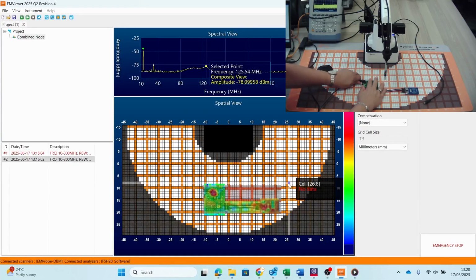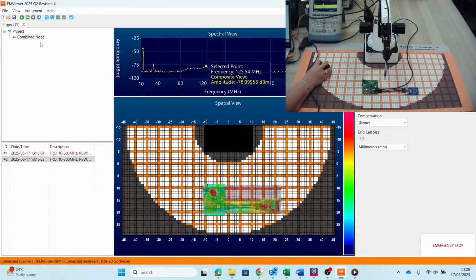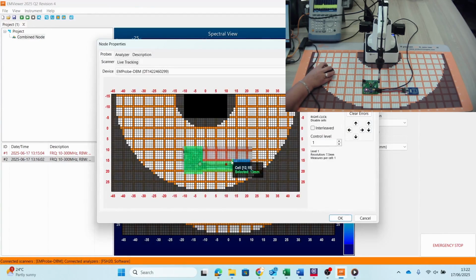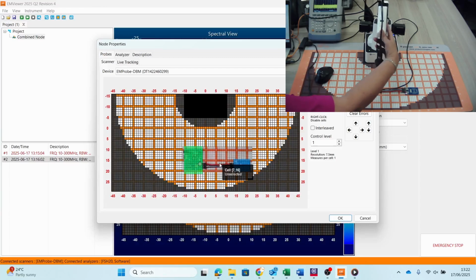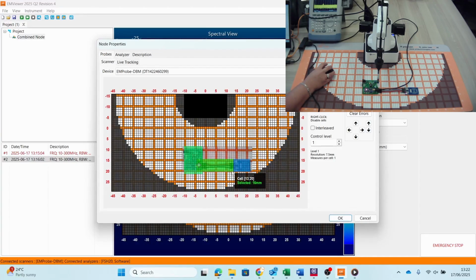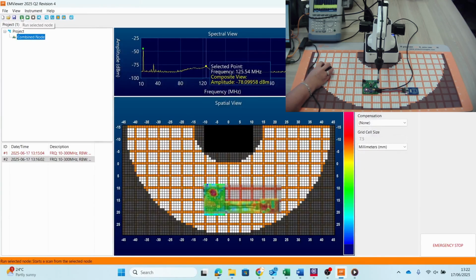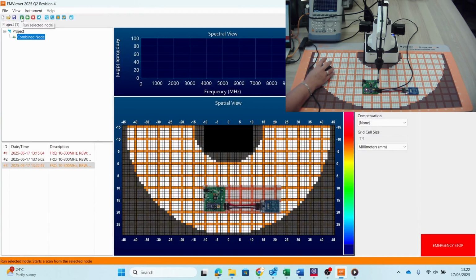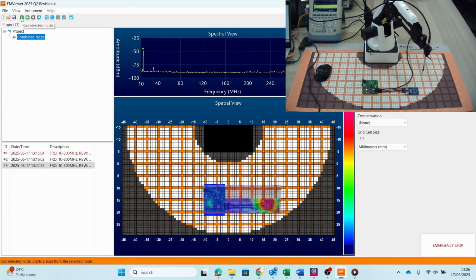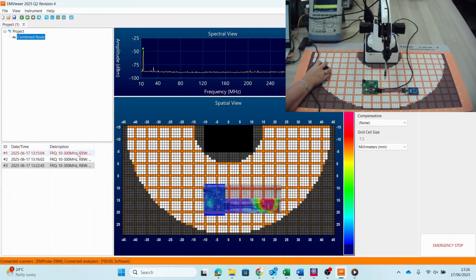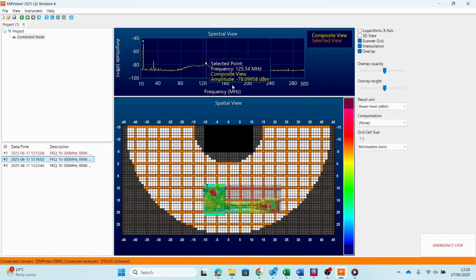Additionally, you can adjust the overlay visuals by moving the opacity and overlay height slider. We are now changing the device's power source to USB. Because of this, we will have to go back into the grid selection and readjust some of the scan heights. Let's perform a scan with our new configuration. Once the scan has completed, we can compare with our previous scan results to see that the noise from the DC to DC converter is no longer appearing.